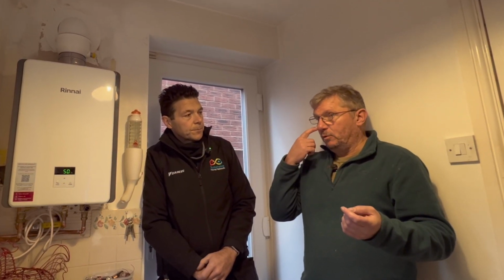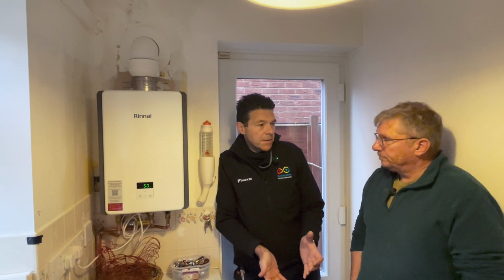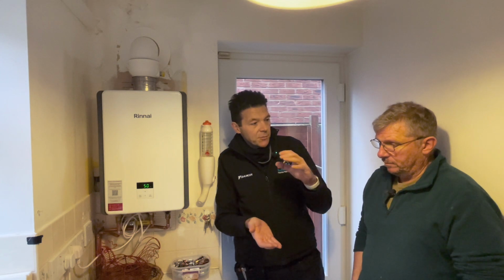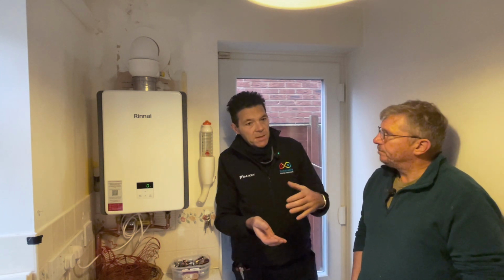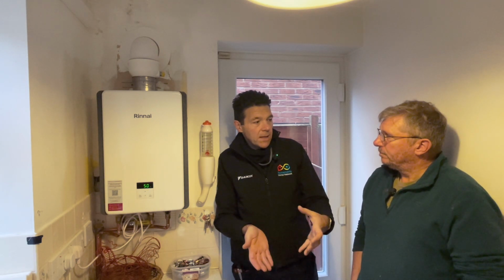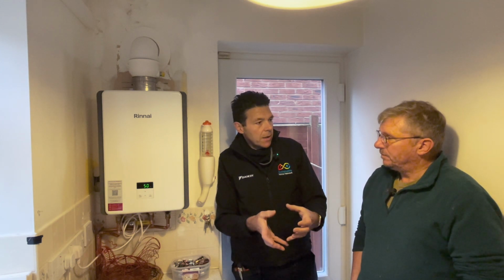When I thought it would be more sensible just to have a heating system for the hot water that would heat the water up to where we needed it, not necessarily past where we need it. Yeah, so most domestic hot water cylinders are set to 60 degrees, and you'll find that due to stratification, you will end up with a slightly higher temperature in the top of the cylinder. So you're using high temperature to store heating source to heat hot water to a high temperature, only to then dilute it again, which would be fine if you had a small cylinder.